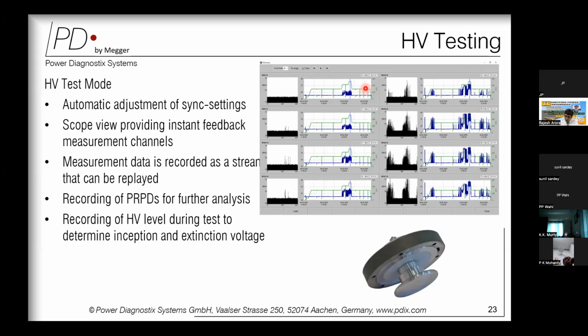So at any point of time, this green volt is a voltage input and this blue is a partial discharge. So we know exactly during the entire cycle of HV test, if during at particular voltage my PD is exceeding the desired level. Like here on the right hand side, some sensors we see that during the maximum peak high voltage, the PD is generated.